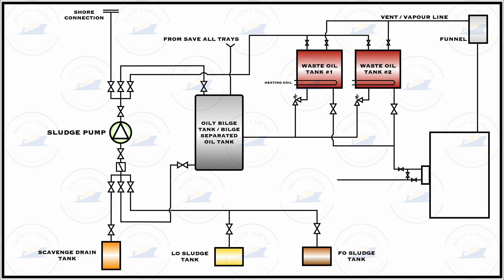Even if a fine droplet gets carried away in the line, it would be caught by the mesh-like or demister-like arrangement present in the funnel area in the mist box section. Once the sludge is free of water content and ready to be incinerated, by lining up the discharge valve of the waste oil tank and the inlet to the incinerator, we align the selected tank to burn in the incinerator. Diesel oil is also used for the initial ignition of the pilot burner, which sustains further ignition of the waste oil.